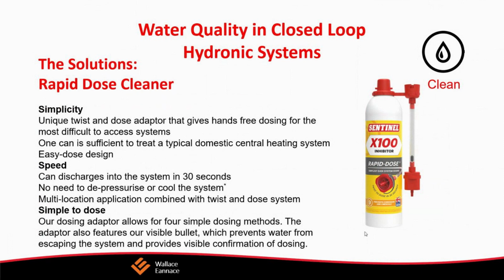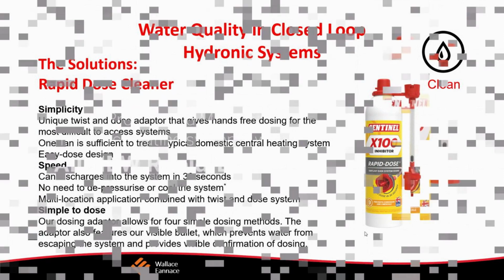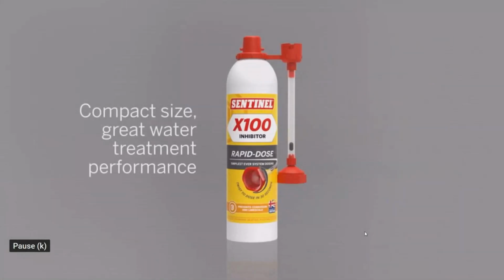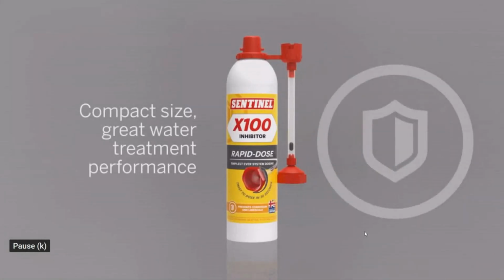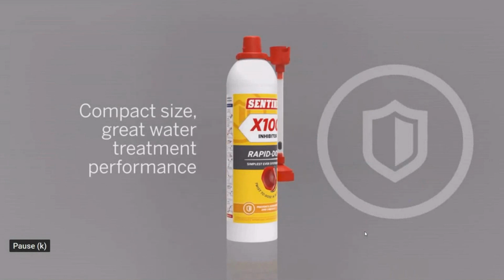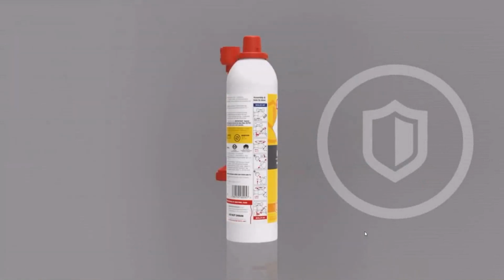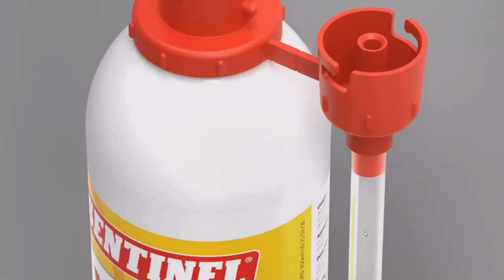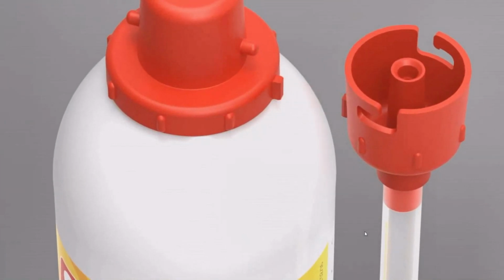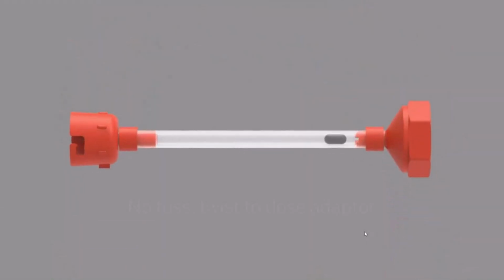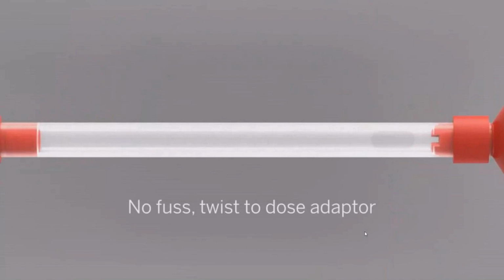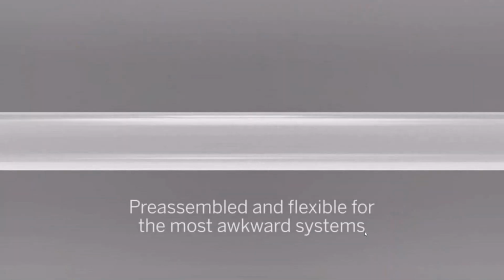It makes a big, big difference. In this particular case, this is straight out of a Baxi Luna UK version of their boilers. But that's standard for almost every single boiler manufacturer in Europe. So water treatment is really critical. I mean, we really want to protect the water, the hot water systems. We want to clean it, we want to protect it, and then we have to maintain it.